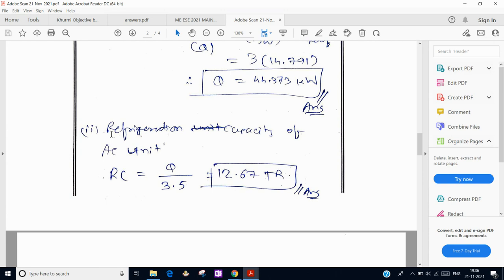For the second question, the refrigeration capacity of the air conditioning unit is found by dividing the total heat gain by 3.5 to convert to tons of refrigeration (TR). So, 44.373 ÷ 3.5 = 12.67 TR. This is the required capacity of the air conditioner.